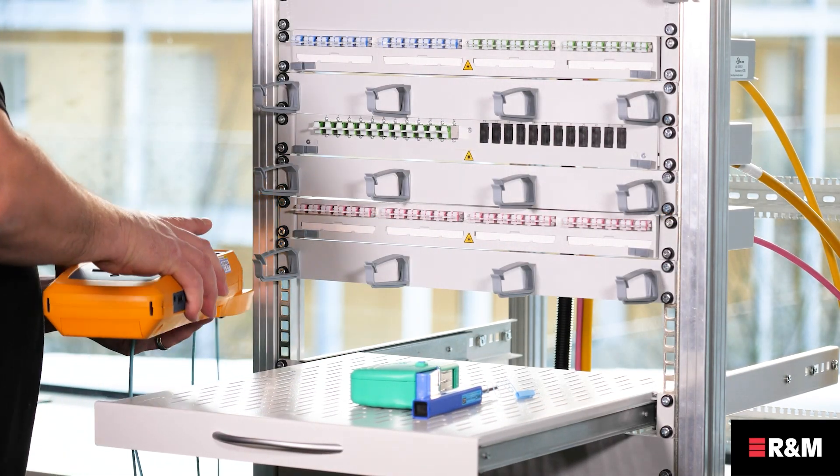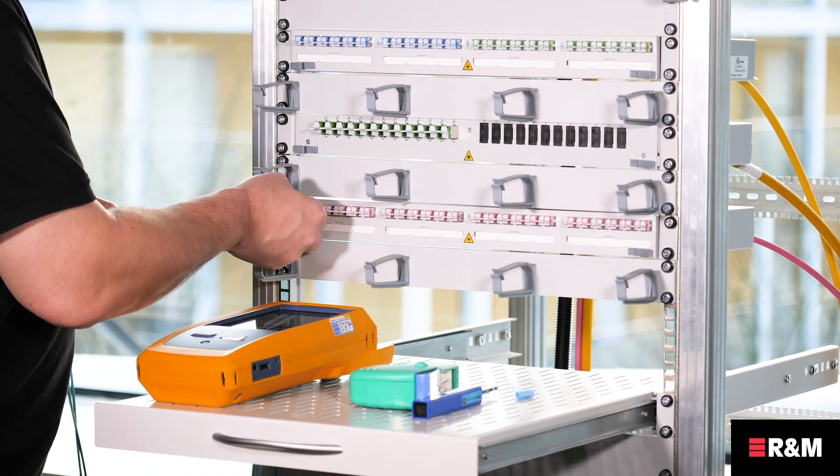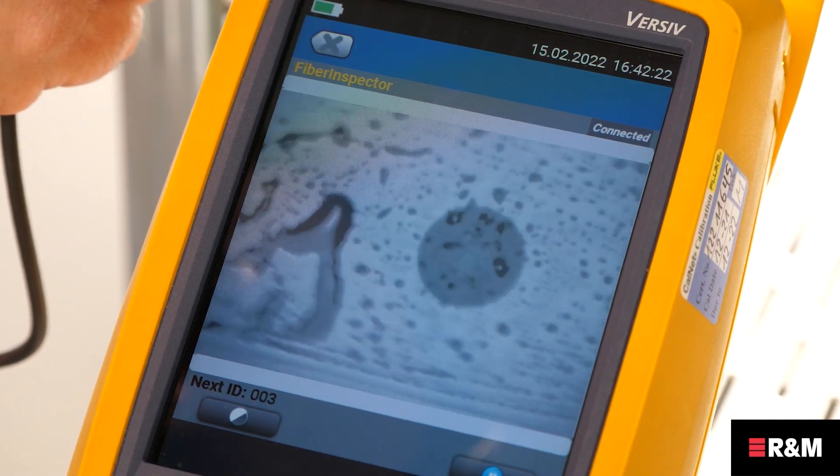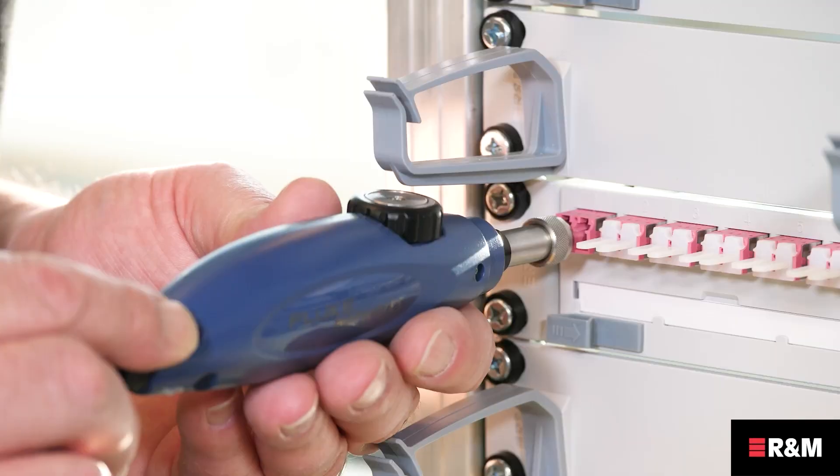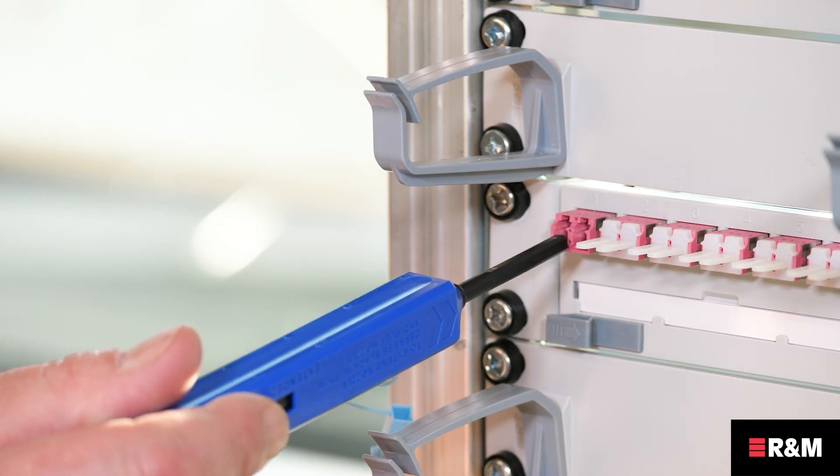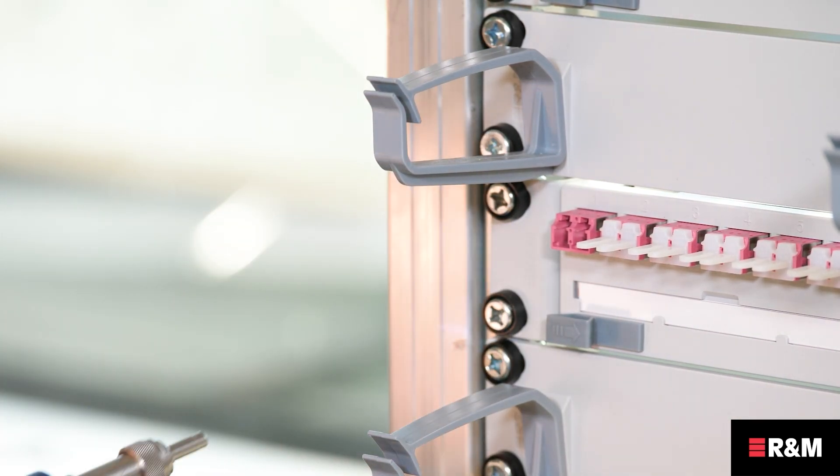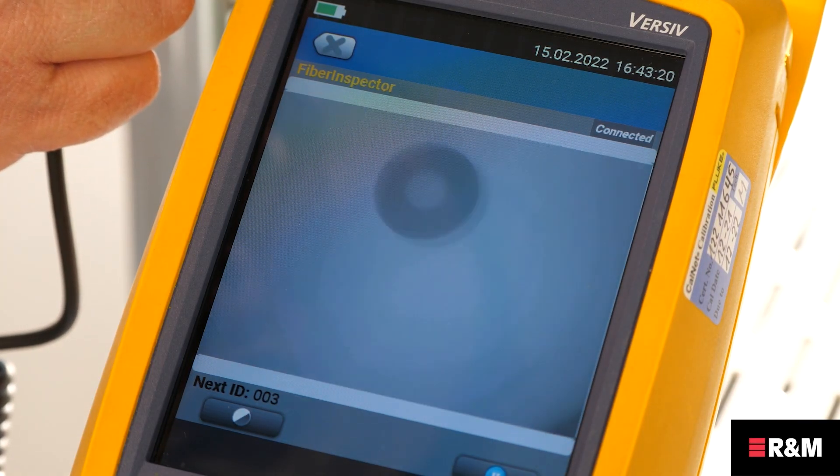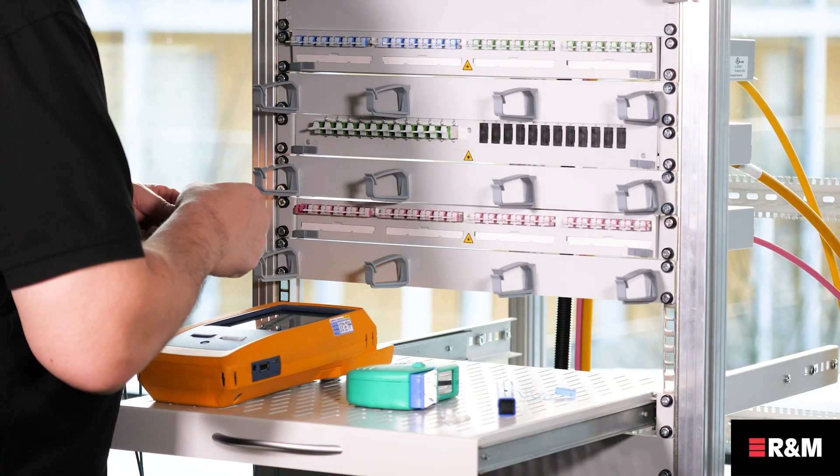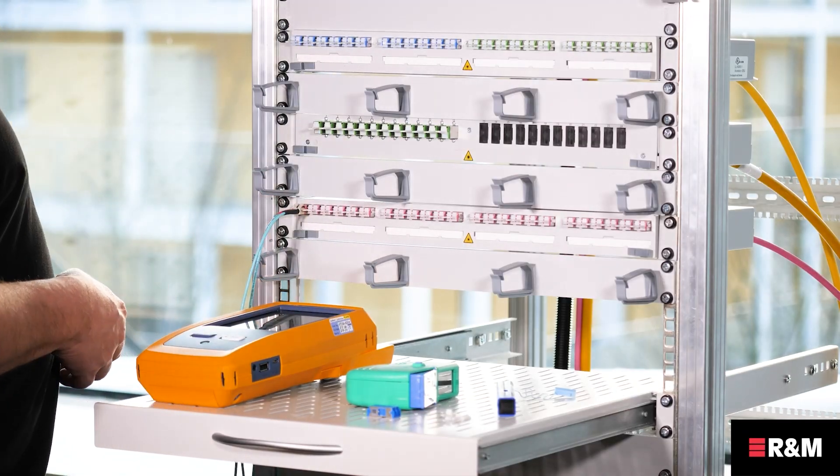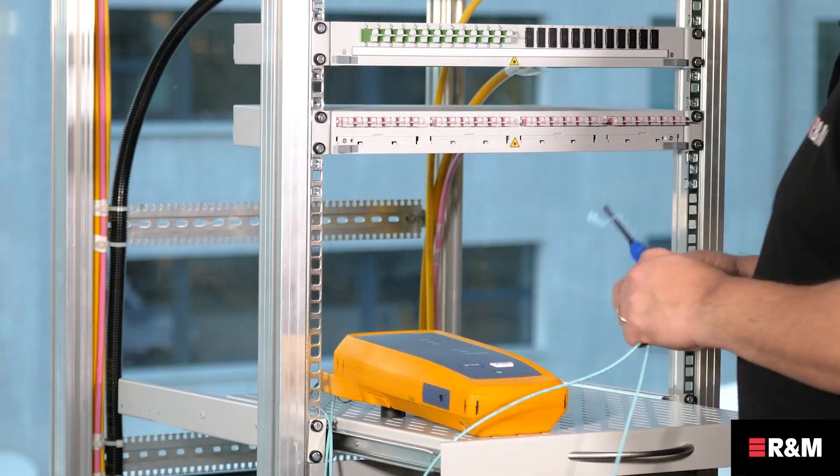Before you start the test, inspect and if necessary, clean the connectors in the panel and the free end of the test reference cord. Remember that when testing duplex links, both apertures of the adapter and two reference cords must be inspected. This needs to be done at both ends of the link. Make the connections and ensure that they are securely fitted on both sides of the fiber link.